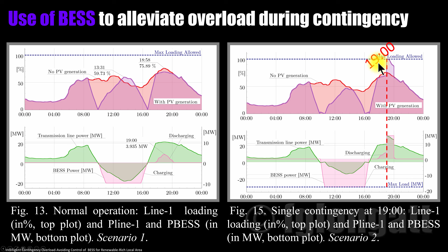Now let's assume that we have the contingency at 7 p.m. At 7 p.m. we don't have sunlight, or the sunlight production is very small, and in that case we can take the advantage of discharging the battery in order to produce local power, minimizing the overloading of the transmission line. As a consequence, in this paper, we designed, implemented, and tested a very specific controller designed to avoid the overload of the transmission line when we have a contingency.